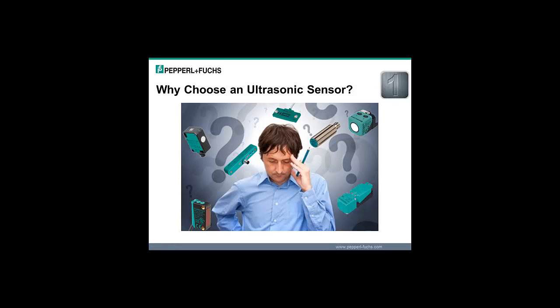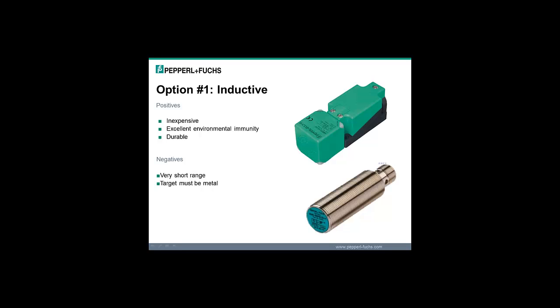I think the most important question to be asked as you start learning about ultrasonics is, why would someone choose to use an ultrasonic sensor? With all the different technologies out there of inductive, photo-wise, capacitive, magnetic, why would you choose ultrasonic sensors? Well, I think in the sensor selection chain of thought, the #1 option for any sensing application would probably be inductive. Inductive sensors are very inexpensive, with great environmental immunity to liquids, oils, greases, sprays, whatever. Very, very durable product as well. But the negatives to these products, they have a very short range, typically less than 50 millimeters, and also the target must be metal. So if you're looking for maybe the level control of a liquid or grains or something like that, inductives aren't going to work for you.